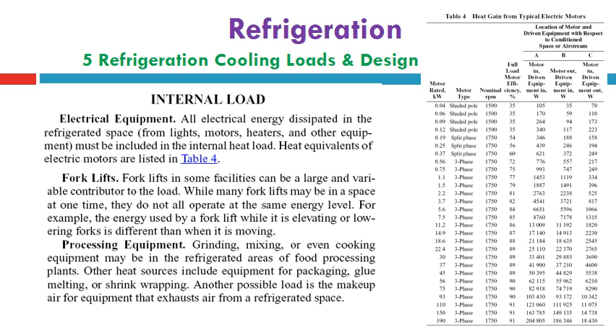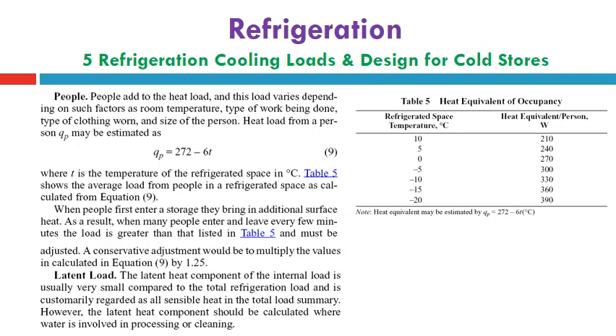Processing equipment, grinding, mixing, or even cooking equipment may be in the refrigerated areas of food processing plants. Other heat sources include equipment for packing, glue melting, or shrink wrapping. Another possible load is the makeup air for equipment that exhausts air from the refrigerated space. All these load components should be considered: electrical equipment, forklifts, processing equipment, and also the people loads listed in this slide.